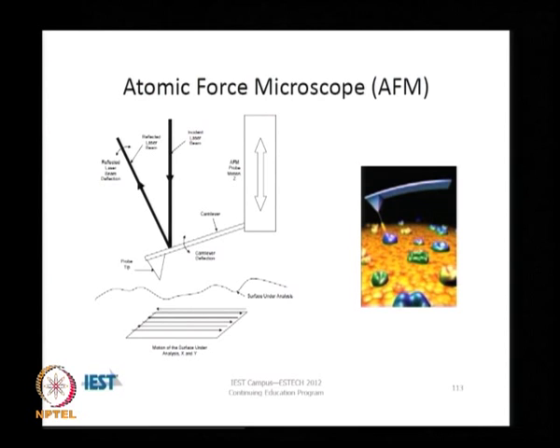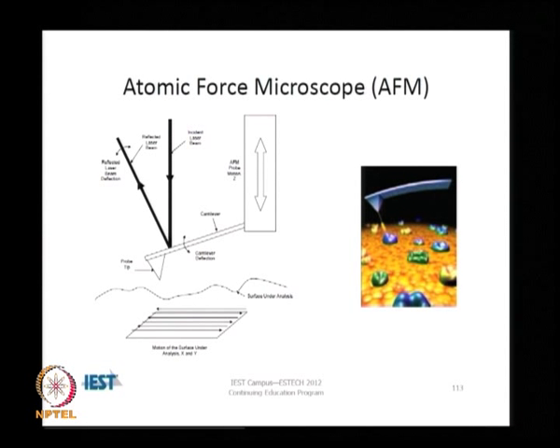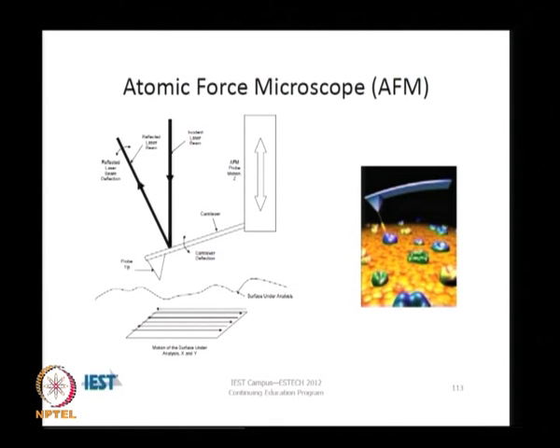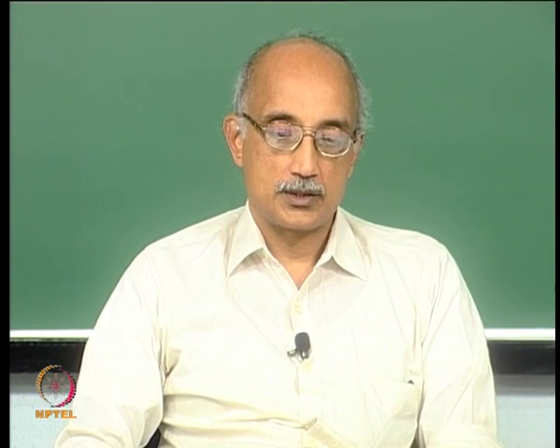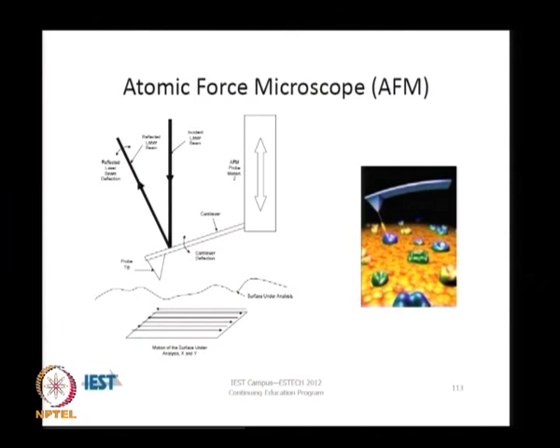The atomic force microscope is specially suited to analysis of nanoparticles because of its ability to manipulate and see matter at nano scale or even sub-nano scale. It consists of a probe that rides very close to the surface — with angstroms of separation between the surface and the probe — making it very sensitive to intermolecular forces of attraction and repulsion. It can very sensitively detect changes in the morphology or composition of the substrate using a cantilever principle. The small deflection of the probe due to induced force is magnified many times, enabling identification and quantification of very small variations in surface topography in three dimensions.